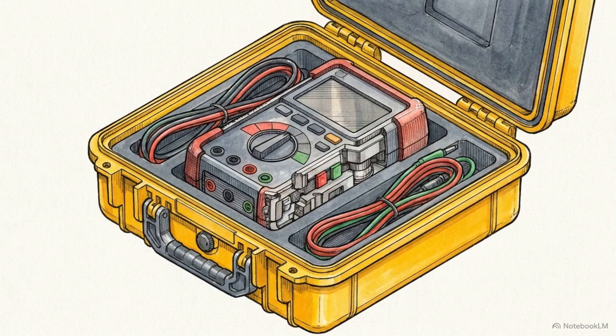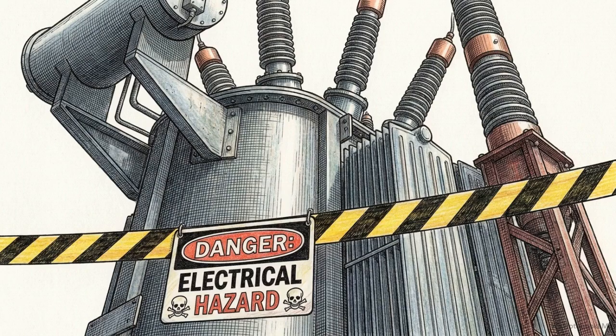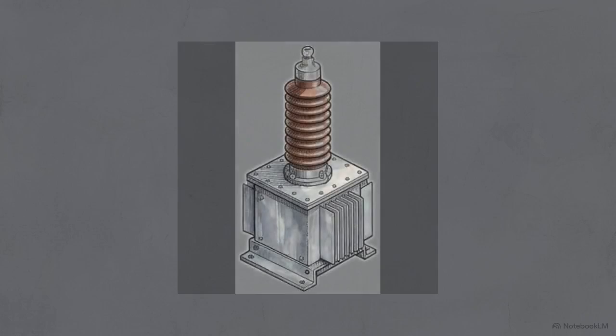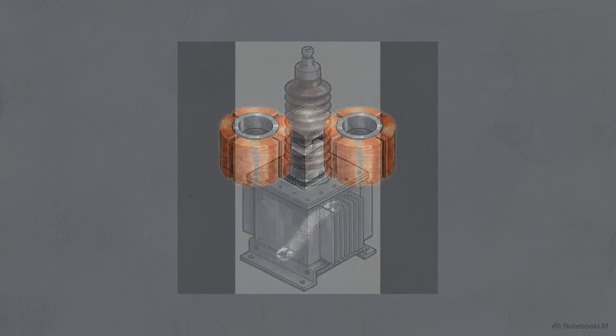Once the environment is secure, operators connect the primary diagnostic engine for these procedures, the Omicron CPC-100 multifunction test set. Failing to properly verify this zero-energy isolated state introduces immediate lethal risk to the operator and permanently invalidates all subsequent test data. The technical sequence begins by proving the dielectric barriers.